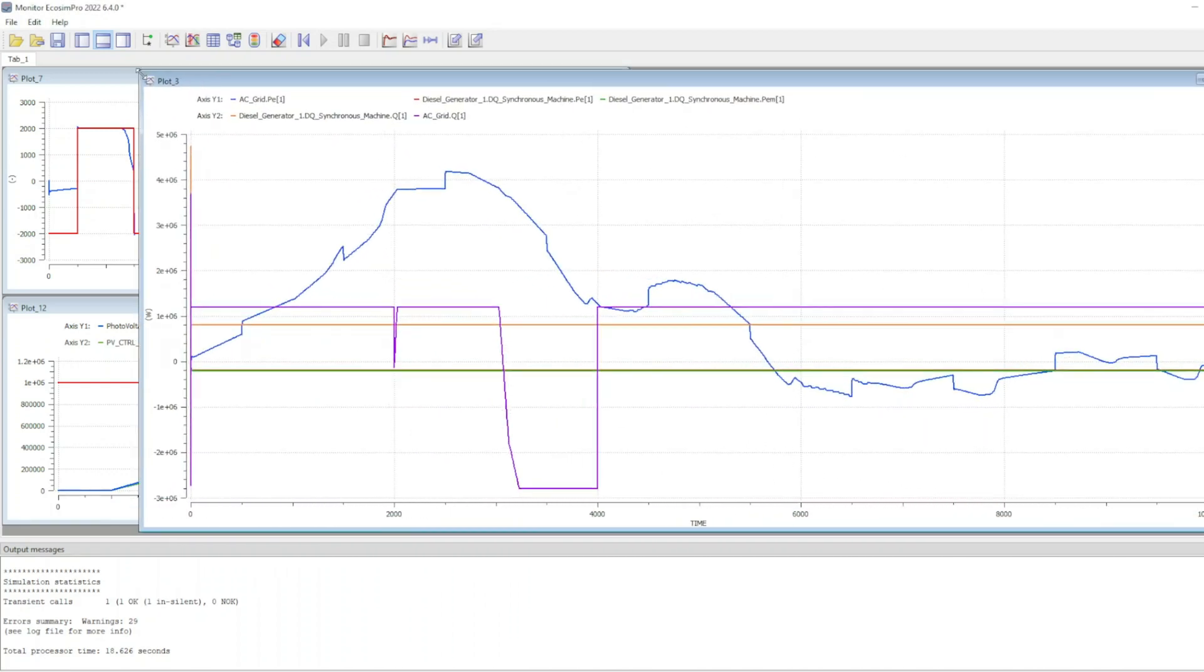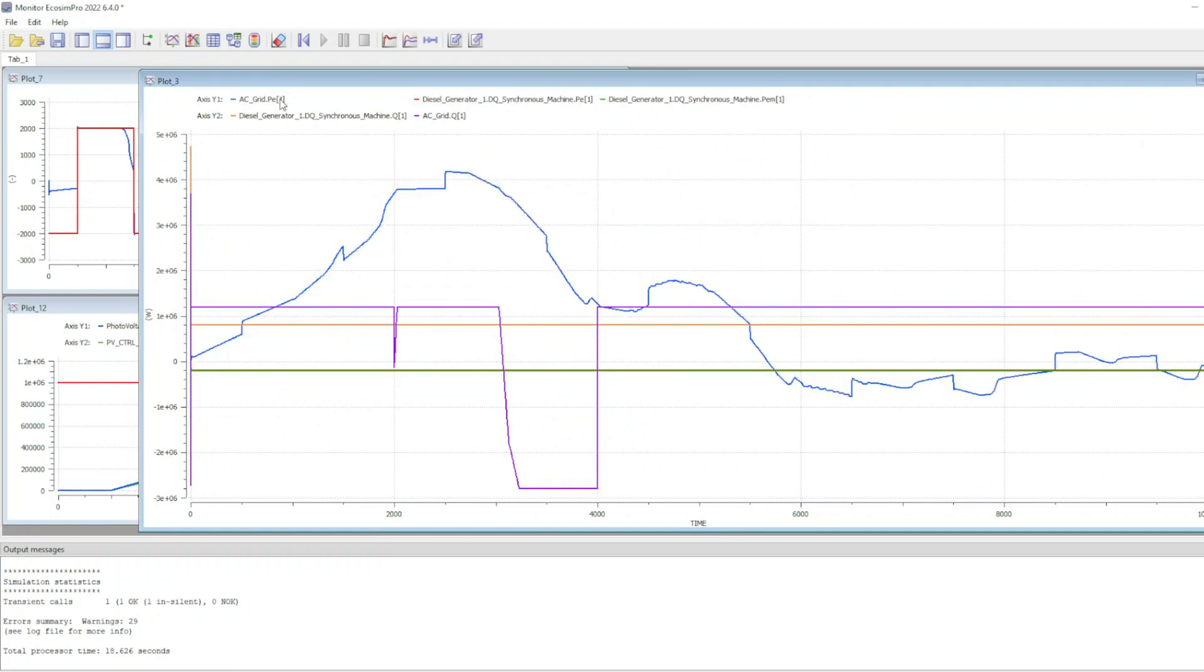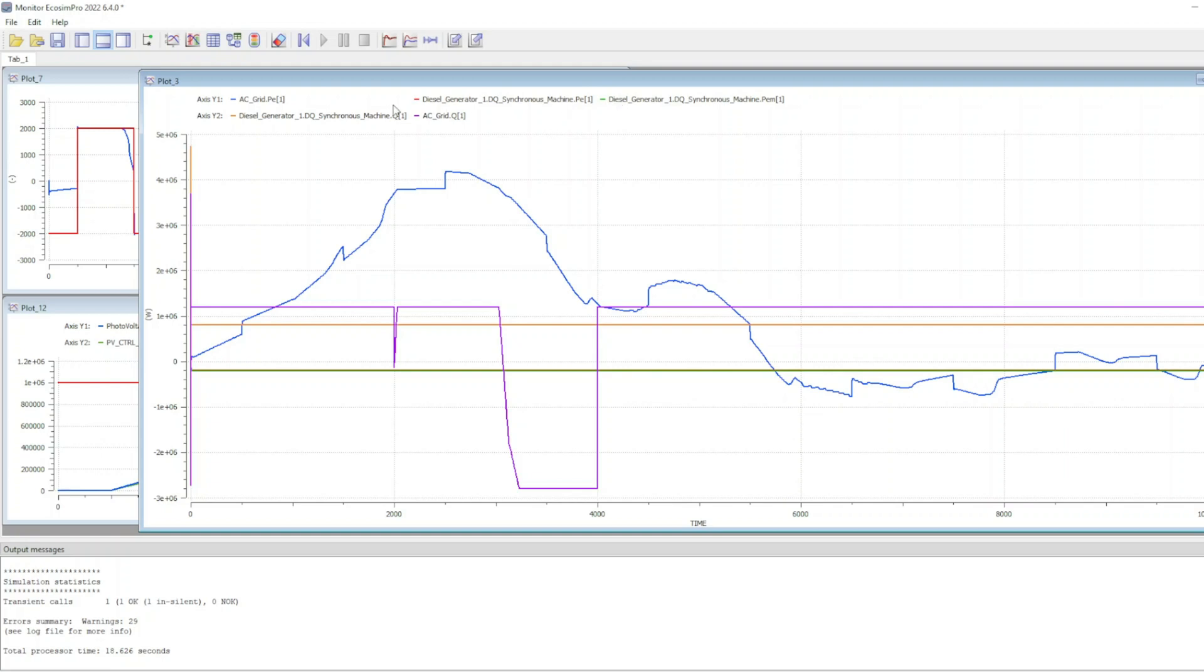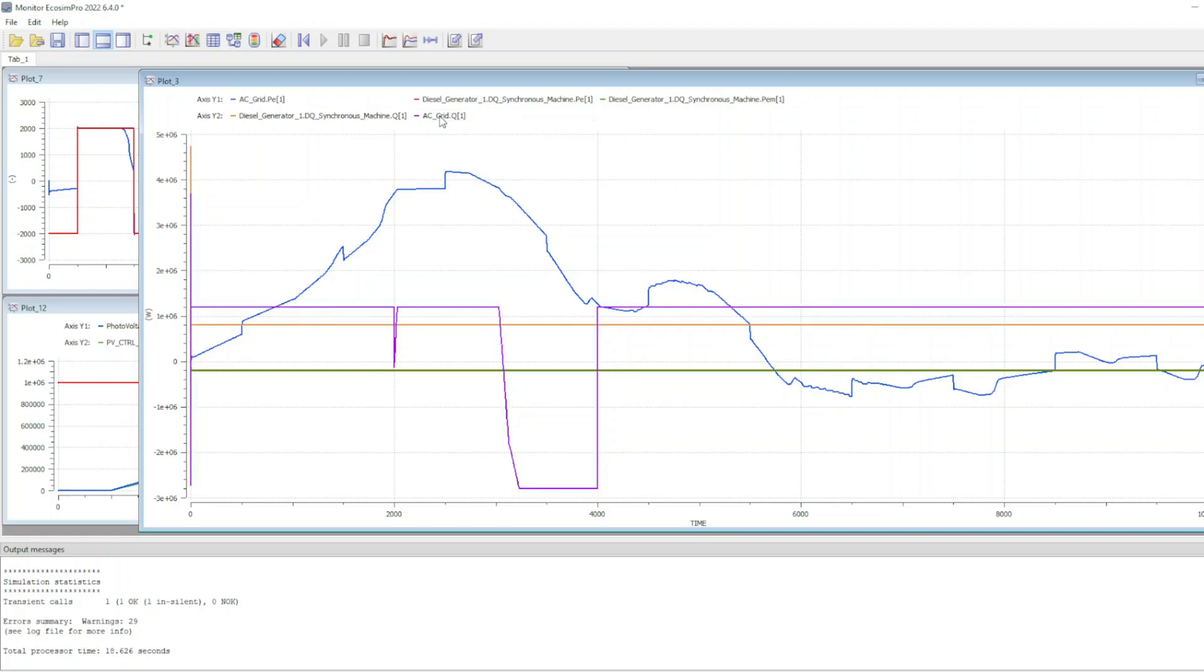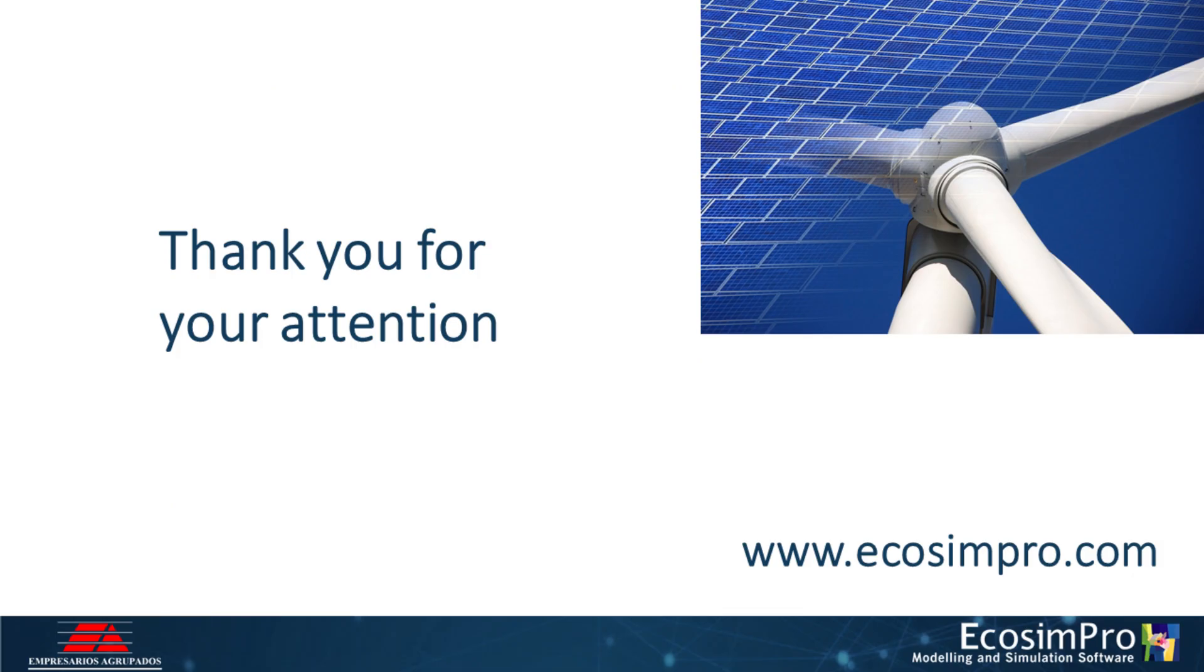Finally, the total active power delivered to the grid is represented by the blue line and the portion corresponding to the diesel generator by the orange one. Additionally, the reactive power is represented in the secondary axis by the violet line.